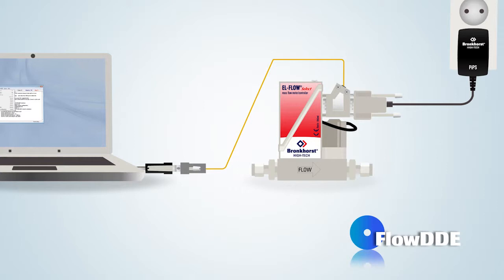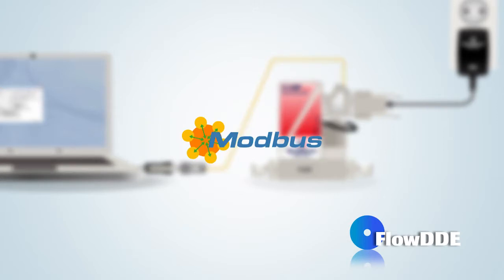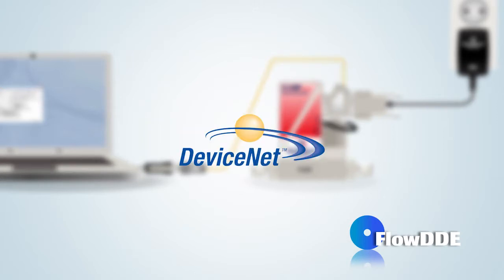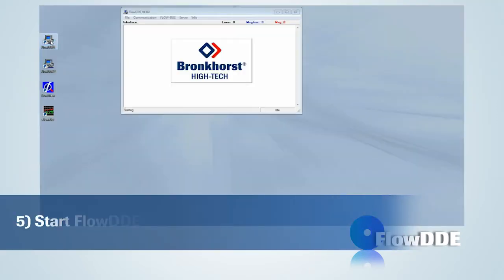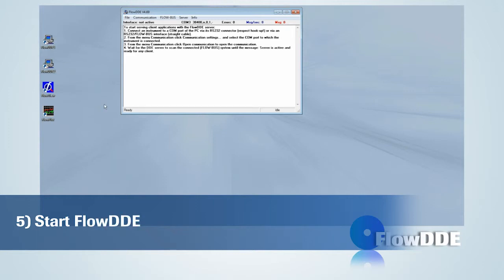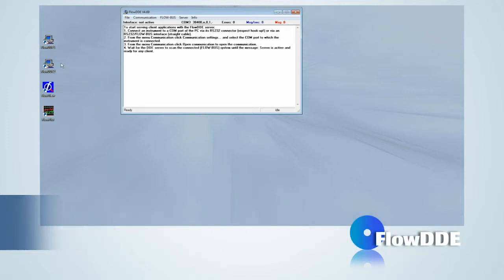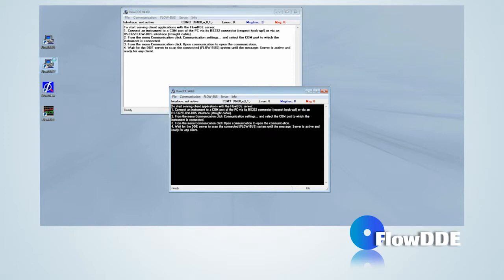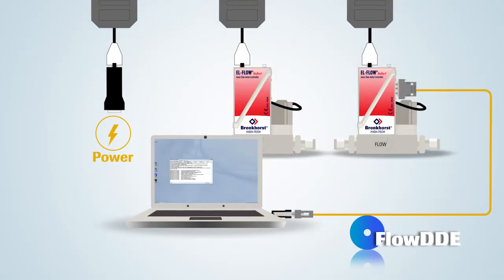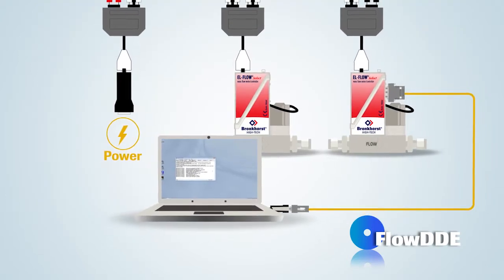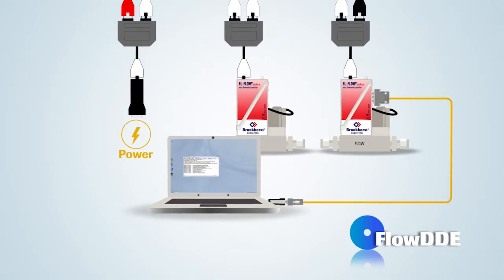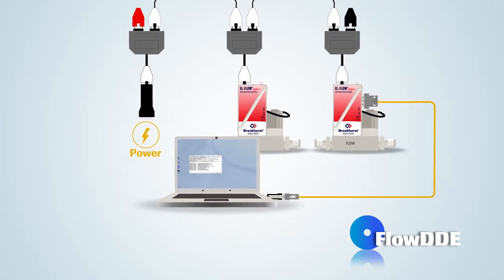This power supply is not required if the instrument is already powered via an optional field bus connection, such as FlowBus, ModBus, or DeviceNet. During installation, two FlowDDE servers will be installed, FlowDDE and FlowDDE Second. Each FlowDDE server can independently communicate with an RS-232-based instrument or a FlowBus system, consisting of one or more instruments with FlowBus interface.